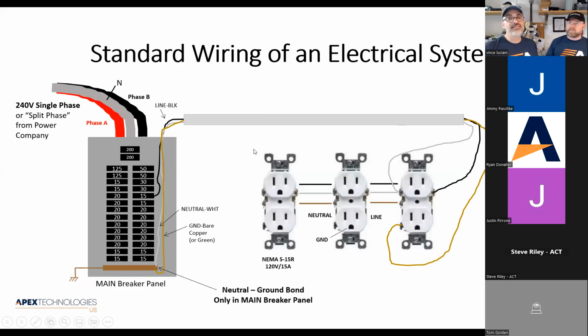The other thing to point out is that these outlets over here are usually cascaded, right? If there was an individual breaker for every outlet and every lighting circuit in your house, your breaker panel would probably be three or four columns long, and it would be very much a waste. Because if you had four outlets in a hallway, what is the likelihood you're going to use all four of them at the same time? Very low. So we'll just put them all on the same circuit. That is okay for a hallway, not okay for a theater closet, right? We want individual outlets. We only want one outlet on one breaker, and instead of a 15 amp outlet, we want a 20 amp outlet, so you get bigger wire, right? Bigger wire, what does that mean? More current handling capability, less losses when there's a large current draw.